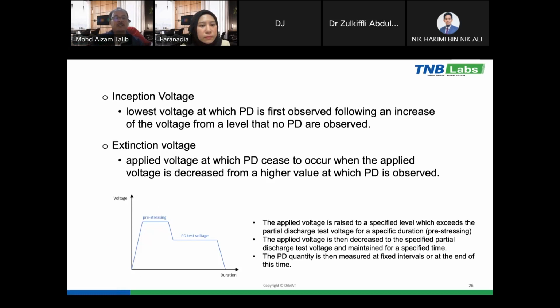And then the other parameter that we can analyze is extinction voltage. Extinction voltage is the applied voltage at which PD ceases to occur when the applied voltage is decreased from a higher value at which PD is observed. So when we increase the voltage, the PD occurs, and then we decrease the voltage until we see there is no PD. The voltage at which PD no longer occurs when we decrease the voltage is called the extinction voltage. So the basic parameters that we analyze are the picocoulomb, inception voltage, and also extinction voltage.